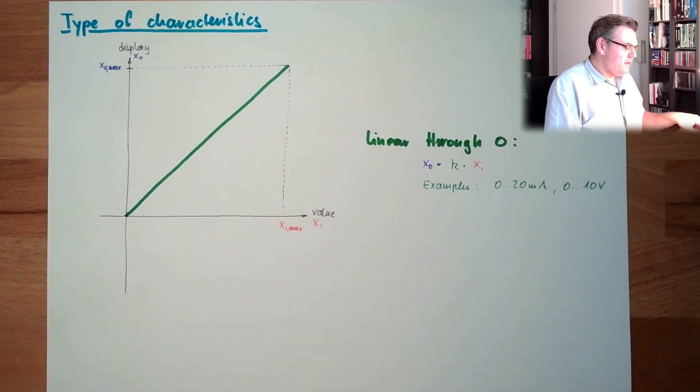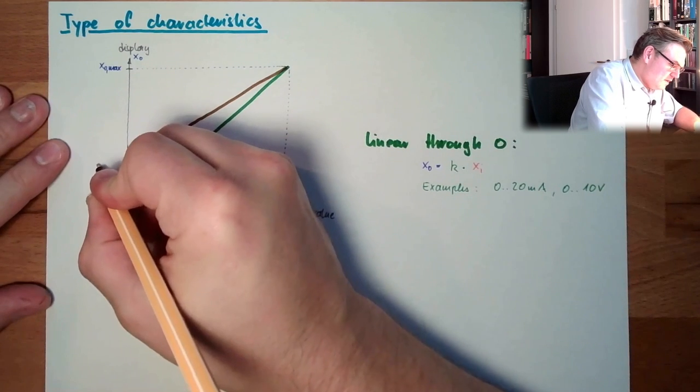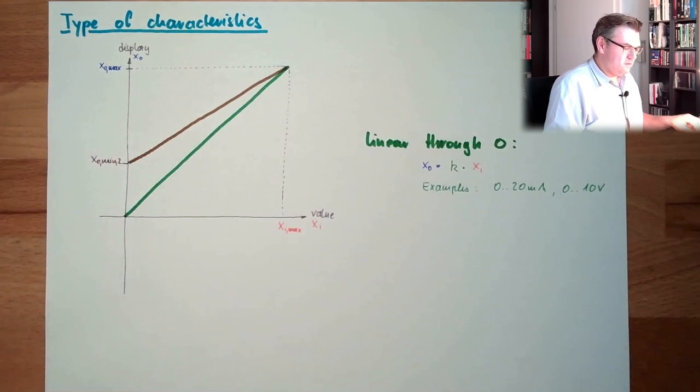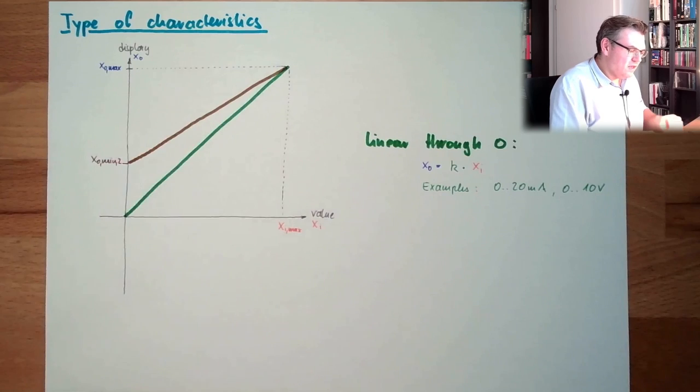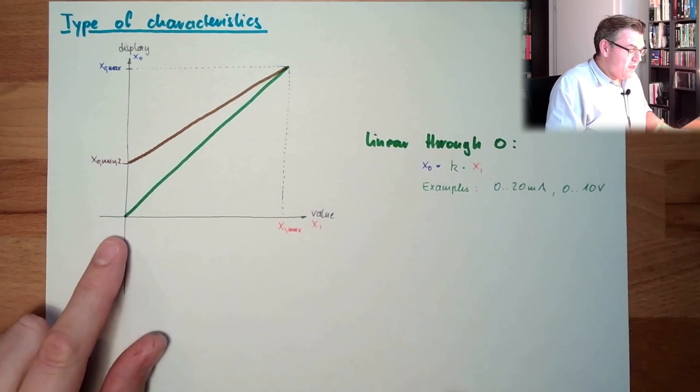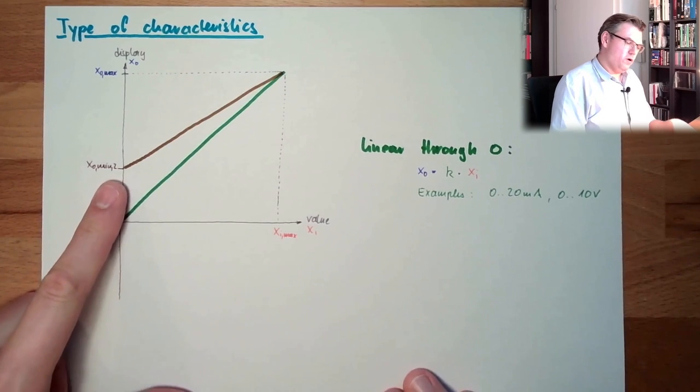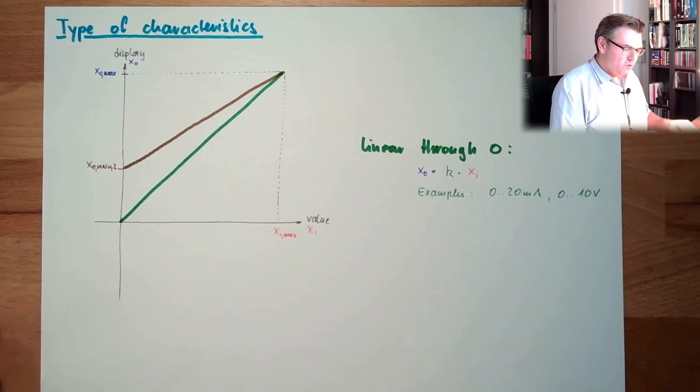Then there's also the possibility, which looks like that, linear. But here we start at a certain position already, and going up. So here we have an offset, here. This is XO min 2, the second. The sensitivity is less, because K is less. It's always the same, however, if we have zero measurement, we already have an output. So if there is zero measurement, the output is already alive. And this is why it's called live zero.